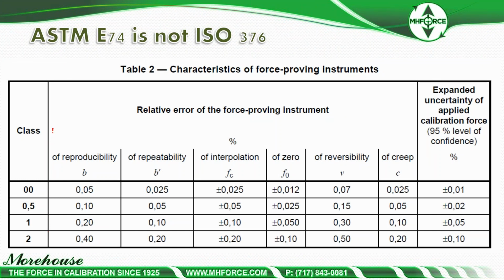Basically, ASTM E74 is doing a lot of things well. And one of the main, that lower limit factor, and what we're doing here is really quantifying what I like to say the expected performance of the device, assuming it's used at the same temperature, under the same loading conditions, everything else. We can stick that load cell force measuring instrument in our dead weight machine. By rotating the instrument, we can get a very good reproducibility. However, ISO 376 also requires repeatability. This is found by putting the instrument in the same location, taking 2 series of readings without rotating, without touching, without doing much of anything. Then we have interpolation. We have 0, how well it comes back to 0. Reversibility isn't always there.